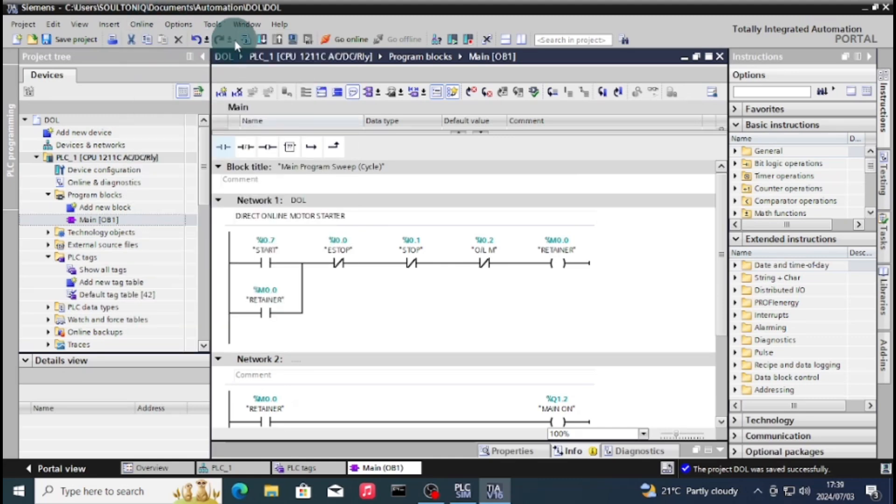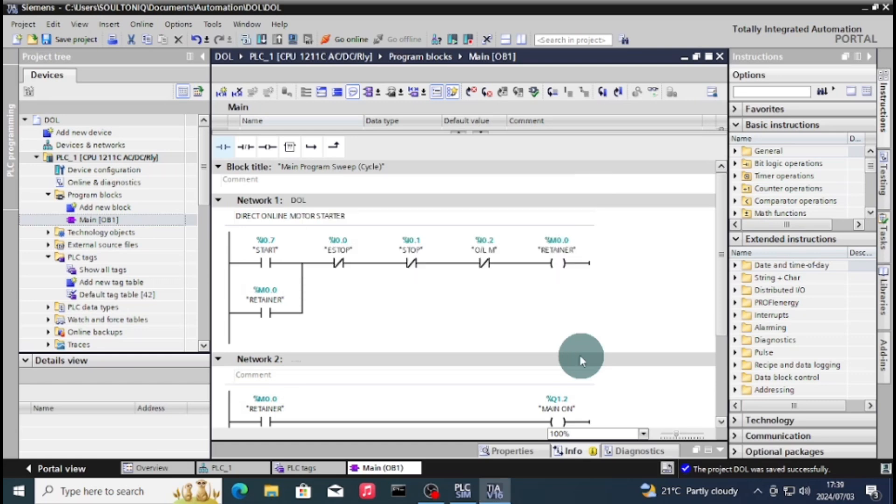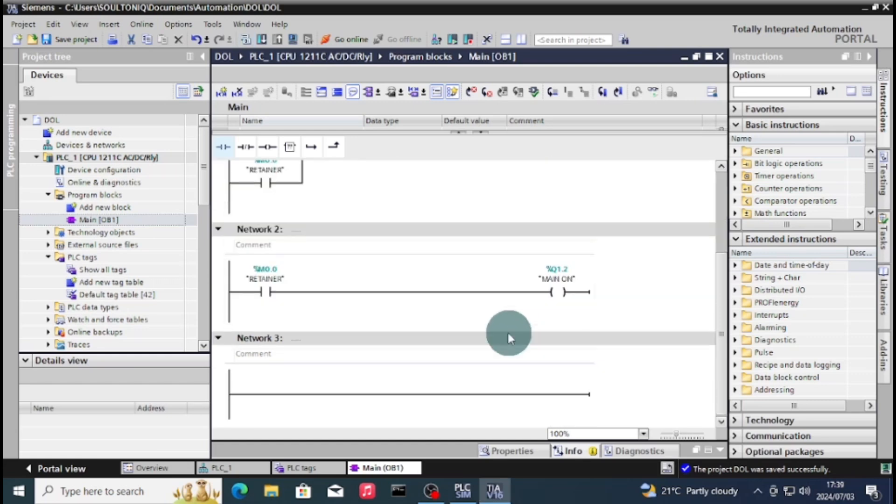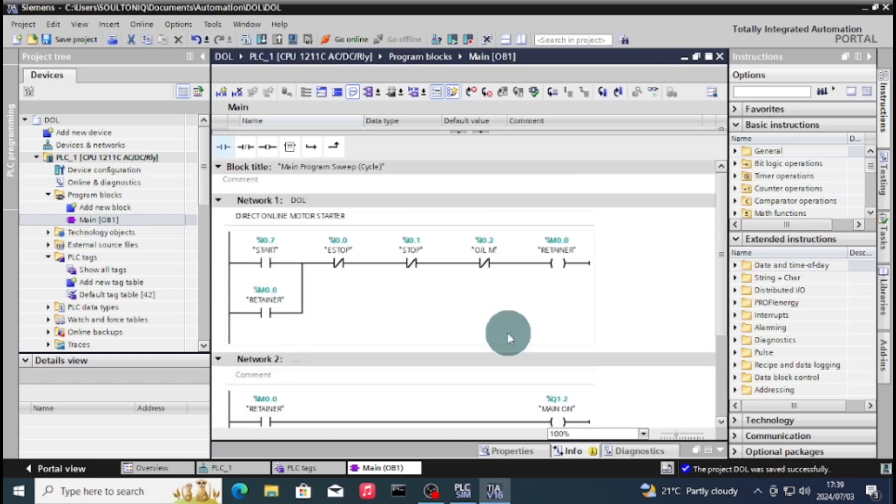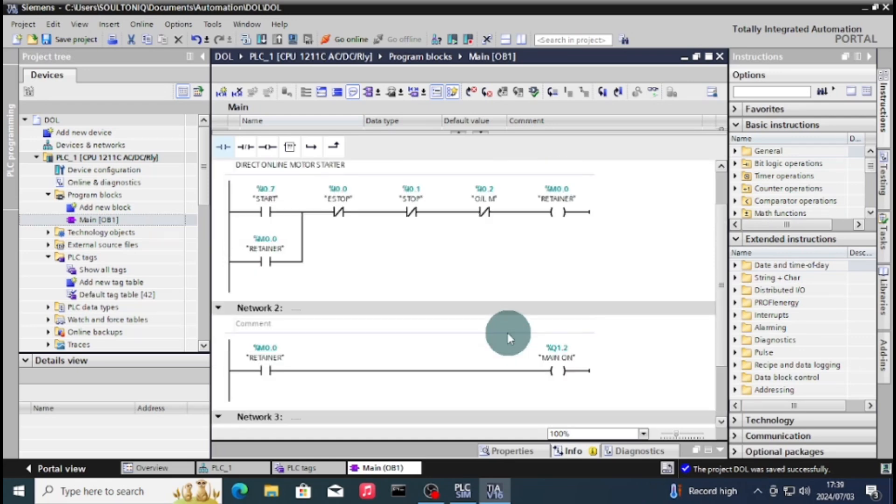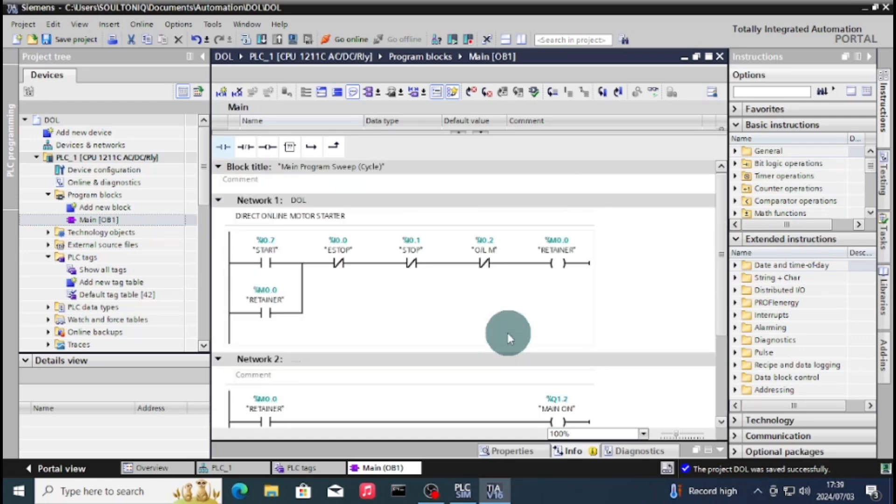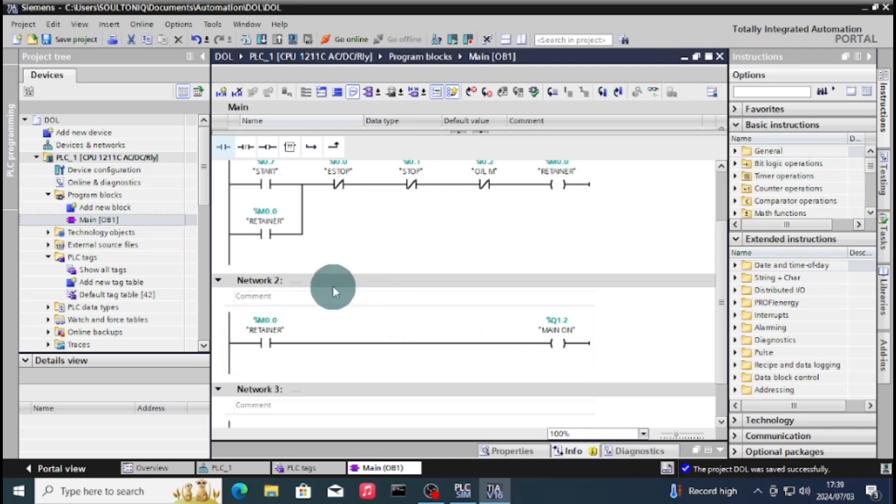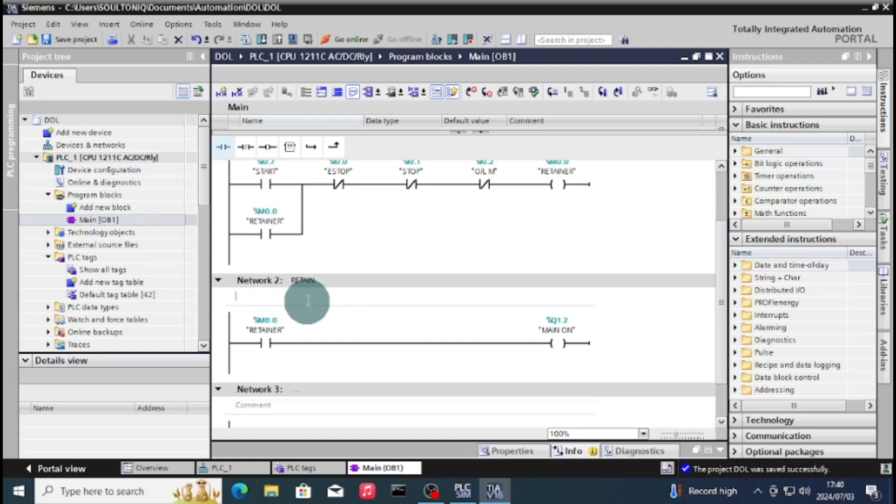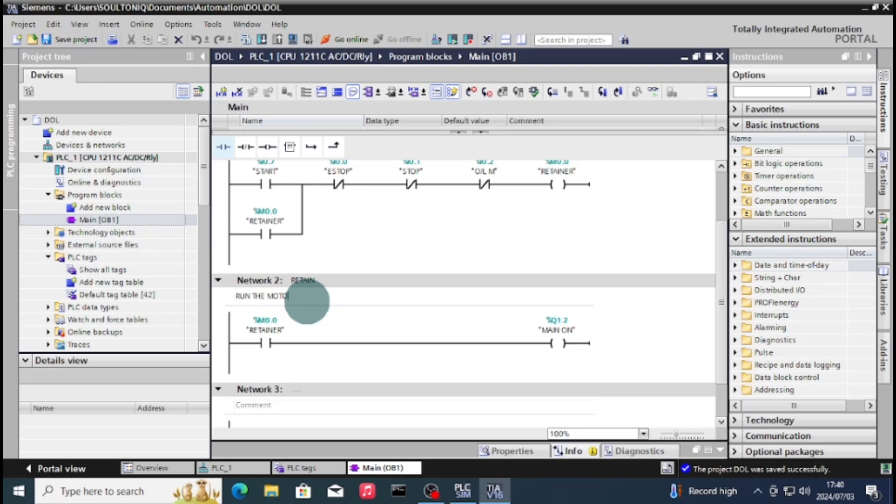So now we are going online. There is also a video on how to use the PLC sim to go online and also add the tags on PLC sim - you can check the video in the description. So this is my project. As you can see, you press the start and you have your stop, then you have your overload, and then you have your retainer. When you press start, your retainer parallel to the start will keep your circuit on and then the retainer will also switch on your main contactor.